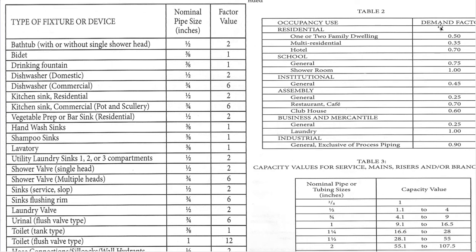In Table 2 you have the demand factor. Typically if you're sizing your own stuff it's probably a one or two family dwelling. So you take your factor value after you add up all your factors throughout the whole house or whatever you're sizing, and you're going to multiply it by 0.5. Some of the larger stuff will be engineered for you, but if you're going to add something on — maybe add a bathroom or laundry room — you'd have to know how to size it this way and plug these into the equation. For today we're going to use a one for one or two family dwelling as an example.